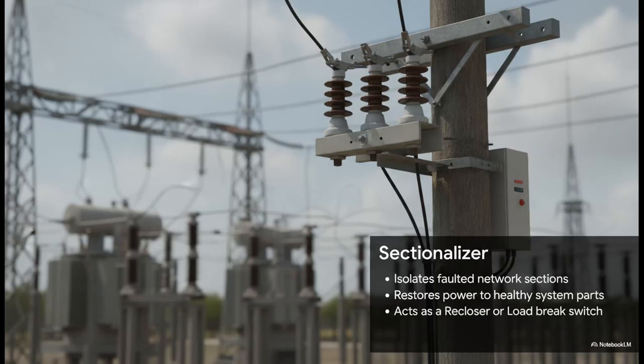So component 8 is the sectionalizer. This can be a recloser or a load break switch, and its job is smart grid management. Imagine a tree branch falls on a power line down your street. This sectionalizer automatically isolates that specific faulted section of the network on the outgoing side. By doing this, it completely prevents a localized neighborhood issue from taking down the entire substation, keeping power flowing to all the healthy parts of the system.